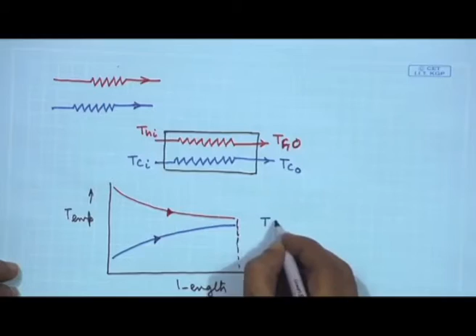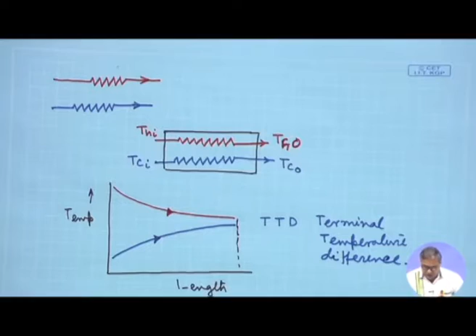There is something very important in heat exchanger, that is called TTD, terminal temperature difference. So, here you see in case of parallel flow heat exchanger, up to a certain point we have gone, that means the temperature difference between the hot stream and cold stream we have reduced up to a certain point, but beyond that we cannot proceed. And if we proceed also theoretically, where we will reach? We will reach some point over here. Let us say theoretically we have reached some point over here, but that is again not cooling the hot stream up to the lowest temperature possible. And this zone is not achievable by any practical equipment. So, we will not be able to achieve this.